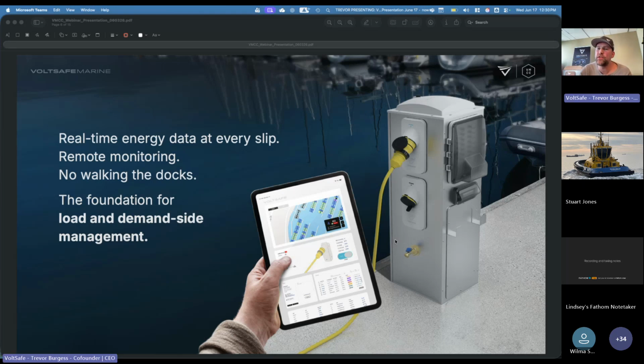In that final design you have things like temperature sensing at the contacts for safety, so that as a marina operator using the marina management system, you can visualize every slip - voltage, amperage, power usage, even billing integration. You're also able to see the temperature at every single connection point in your marina, in real time, and set the entire marina system to a maximum preferred temperature, for example 100 Celsius. If it goes above that, it will automatically turn off.